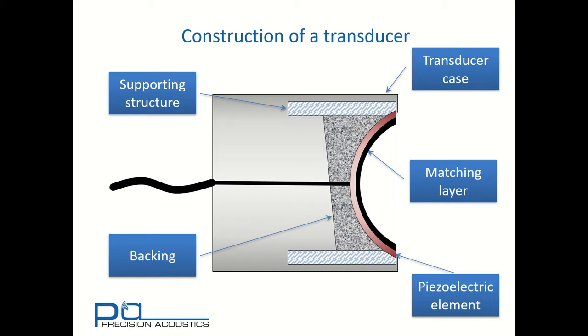There'll be a connection to the rest of the drive circuitry, and this may well travel via some form of impedance matching network. It's important to realize that many of the aspects of this transducer construction, but specifically the piezoelectric element, the backing, and to some extent impedance matching, can introduce damping.